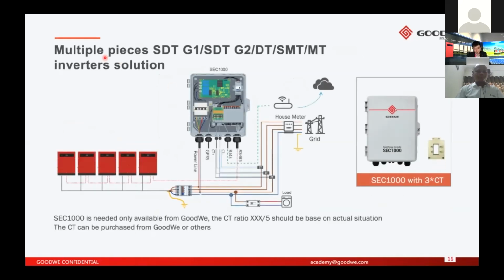And here is the multiple pieces case. If your system is a C&I system or has multiple inverters, you can only use the SEC1000 from GoodWe to do the export power limit, like multiple pieces of SDT-G1, SDT-G2, DT, SMT, or MT series. Like here, multiple inverters, so you can only use the SEC1000. The cable connection is the same as the last slide. And as I already mentioned, the CT can be purchased from GoodWe or from your local market. But remember, the CT ratio should be a number divided by 5.